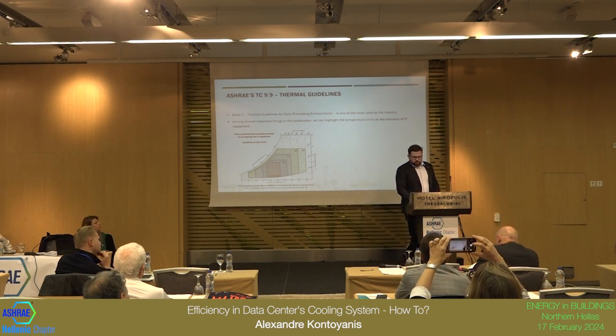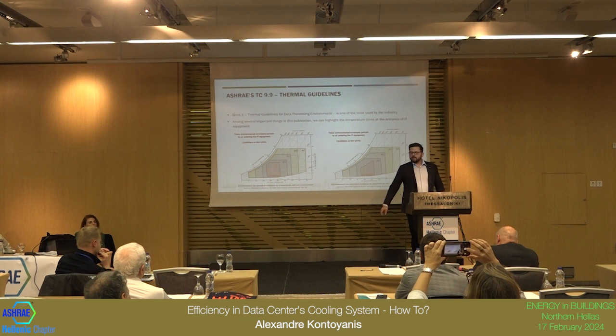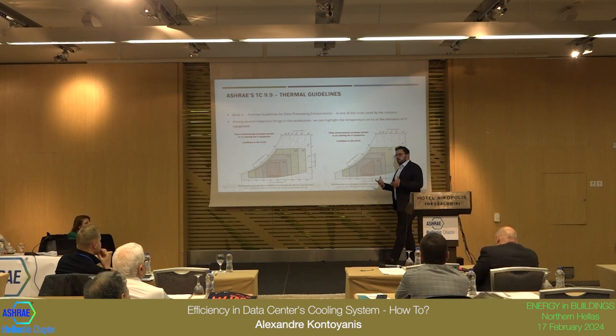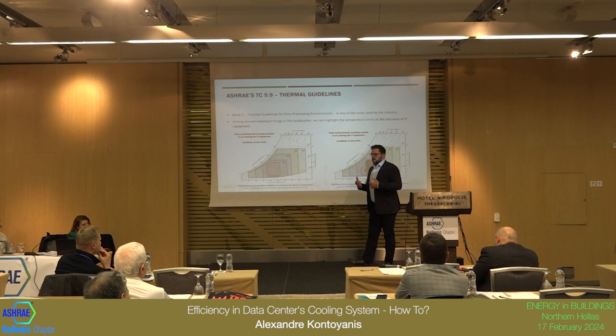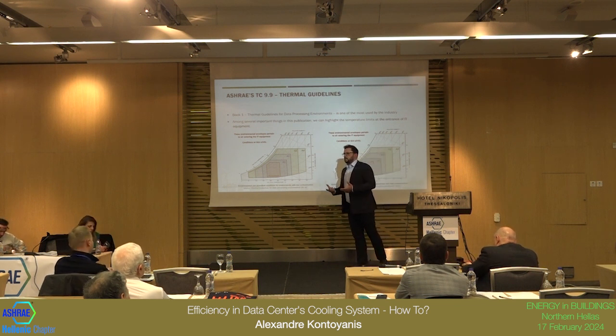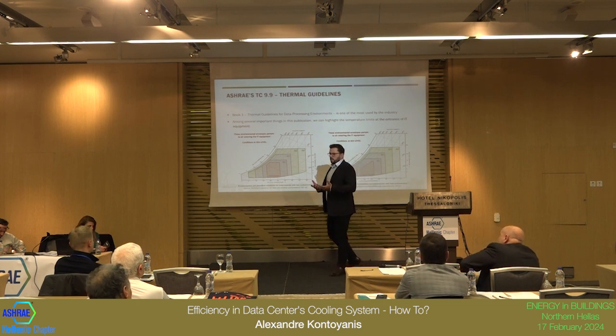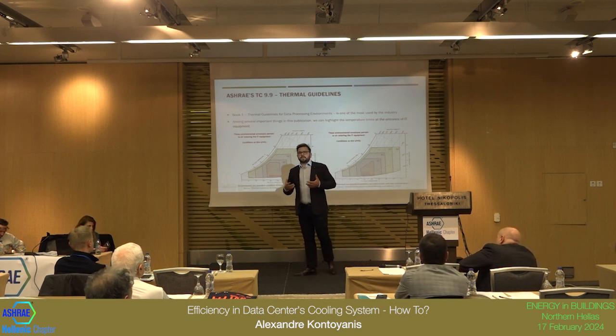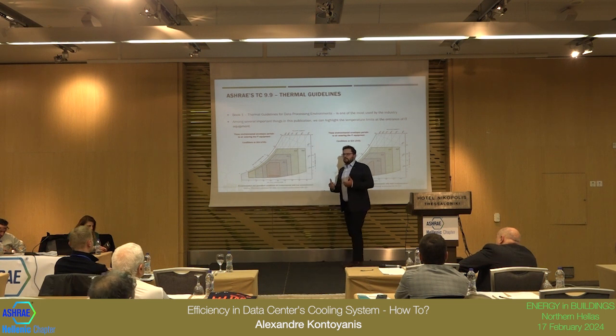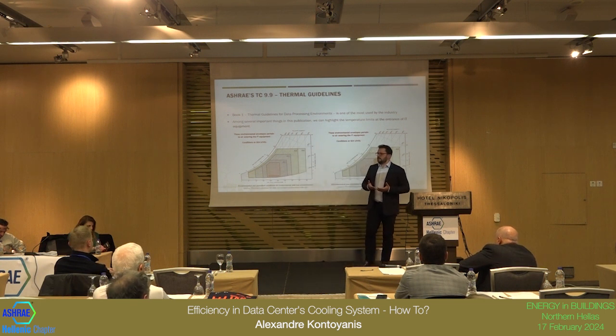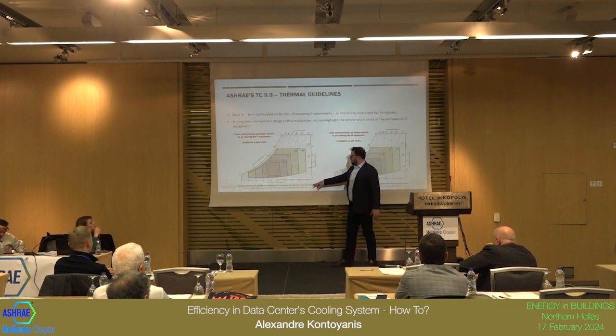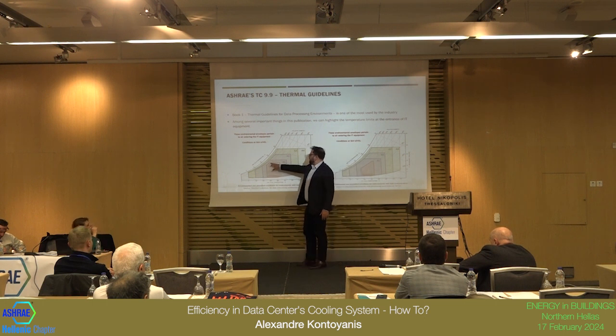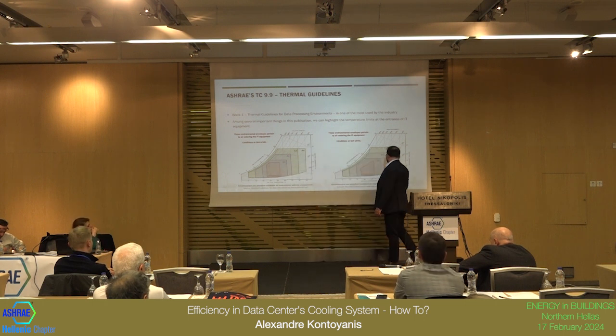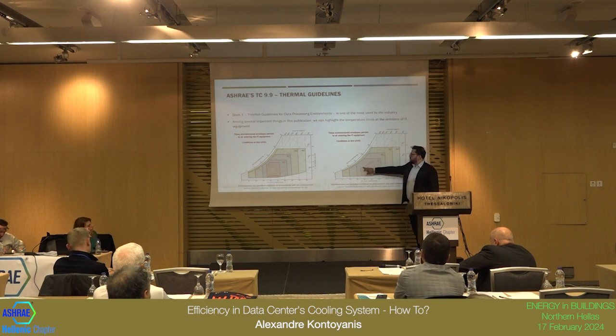In the last edition, we just made an update. ASHRAE always funds research on what the industry is asking. And one question is, if I have a high humidity environment, what does it affect? And we found that it affects the corrosion of the IT equipment. And we found that if you have an environment of low contamination, you can rise up to 70%. But if you have a high contamination environment, you should drop to 50%.